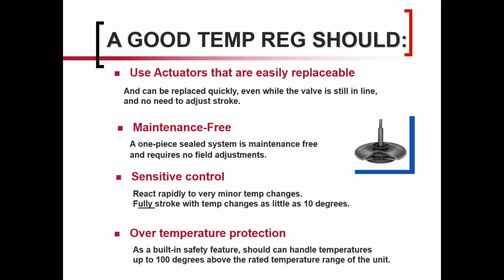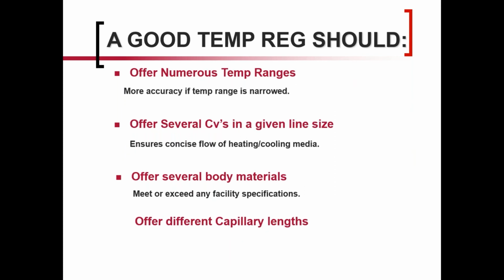And going back to that one example, if it's 180, what happens if something goes wrong in the system or with the steam supply or the thermal system, and the actual valve goes above that, the water that the bulb is in goes much higher? Well, a good temperature regulator will have over temperature protection, typically to 100 degrees, so that if, again, using the previous application, if that got up to 275, then you're still not going to damage the actuator or the assembly because of over temperature protection. So a good thing to watch for if you're ever specifying one of these.